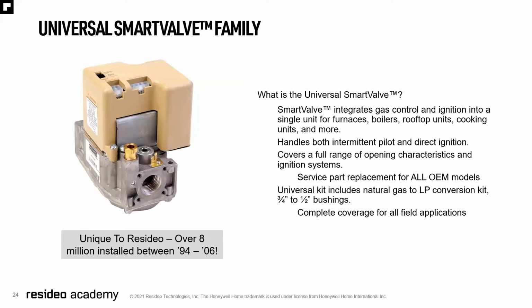Universal smart valve family. What is a universal smart valve? It integrates gas control and ignition into a single unit for furnaces, boilers, rooftop units, cooking units and more. Handles both intermittent pilot and direct ignition. Has a full range of opening characteristics and ignition systems. We sell replacements for all OEM models in our smart valve universal family. We include in the kit, whenever possible, an LP conversion so that you can change it from natural to LP if needed, as well as 3/4 to 1/2 inch bushings. Complete coverage for all field applications.